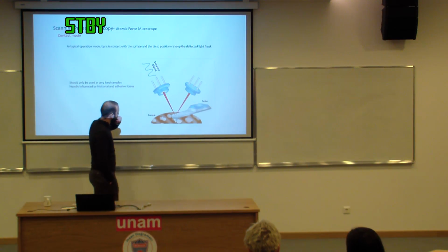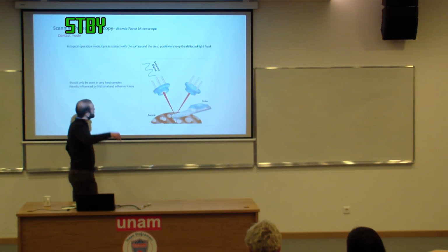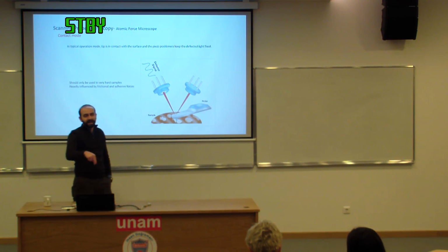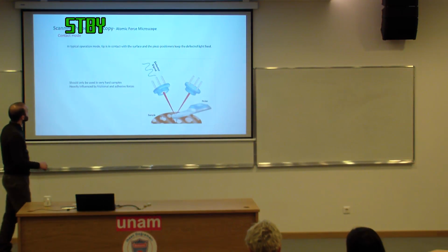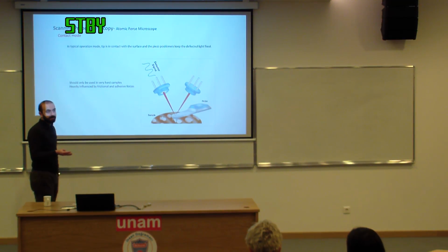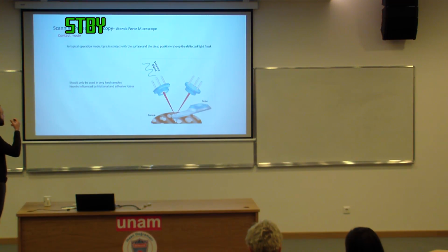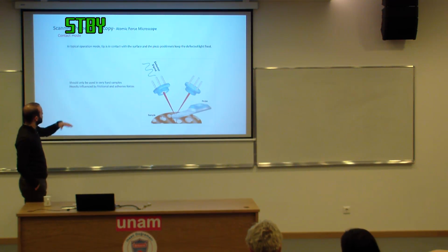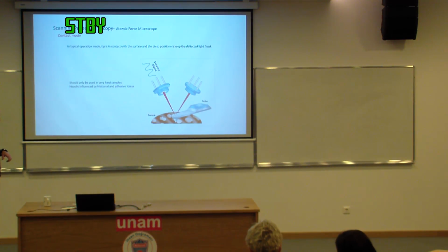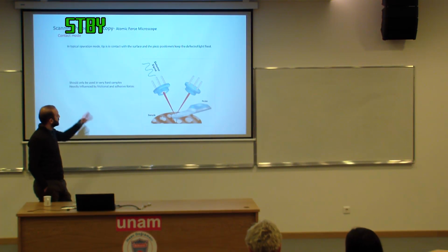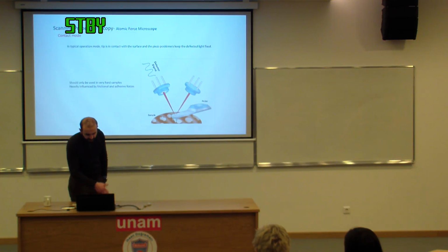Let's talk about contact mode first. You have this tip. As the name suggests, you lower the tip to a point where it's in contact with the surface. This is an aggressive technique. Your tip needs to be hard. It shouldn't be a soft material. And your sample needs to be hard. This technique is heavily used for measuring friction and related forces. Nowadays, not many people use contact mode. We use it from time to time to measure the thickness of atomic layers. But really, contact mode is something that you should stay away from.